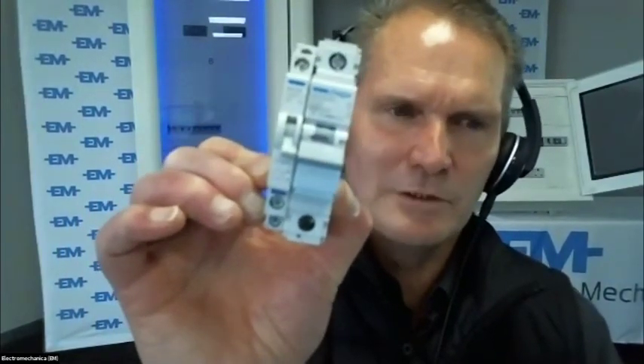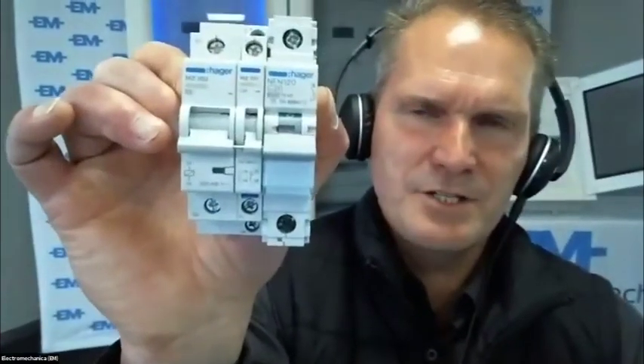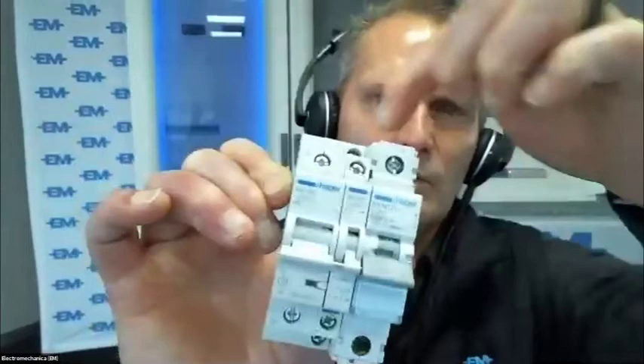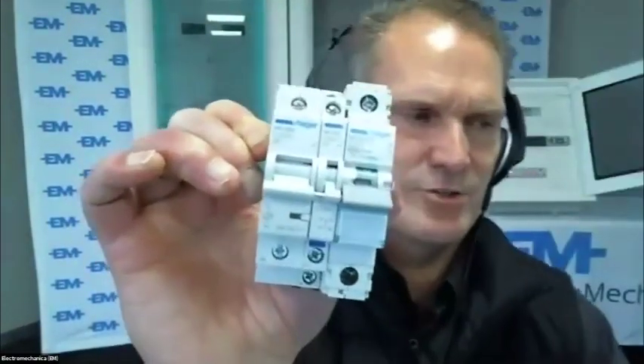But even now, if you would like to add a shunt trip to this, it's still possible. Again, I've already removed it. There's a small cover that closes the entrance there. So you can then take your shunt trip, exactly the same. You clip it onto the product, okay? At the bottom, the same mechanism, you just open it and you lock it into position. And now you've got a miniature circuit breaker, auxiliary contact, normally open, normally closed, and a shunt trip if you want to remotely switch this product off, or a safety emergency stop button to trip it.